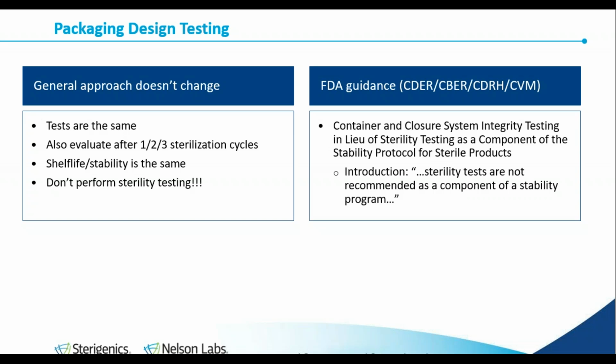So generally the tests are the same that you're looking at doing after thermal sterilization. You may want to add an evaluation that, with some sterilization methods, sometimes there's a benefit in validating ahead of time that you can sterilize through 2 or 3 cycles and that the product and packaging are still fully functional. So that's something additional to consider.